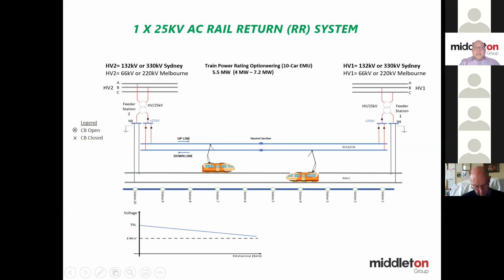And of course, in addition to that, you will have to look at the rail voltage, make sure that it's safe for the passenger to use, and also any leakage current to any DC railway that is running adjacent to it or at 90 degrees to it. And you will need to look at whether the 50 hertz current and its harmonics are going to interfere with the track circuits, which are the train detection system on the existing DC railway.